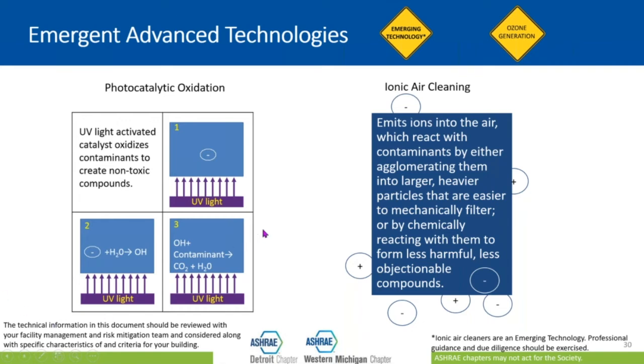With these two technologies, you want to be careful of a couple of things. One, in particular, the photocatalytic oxidation. It does use UV, but it doesn't always use UVC, which is the band that is most effective at getting rid of the microorganisms. Sometimes it does use UVA or UVB. And some studies indicate that it is very effective. Some studies indicate that this is not that great of a technology. There are not a lot of studies done in the HVAC arena with these technologies. They've been done in laboratory settings, but not specifically looking at HVAC test setups.